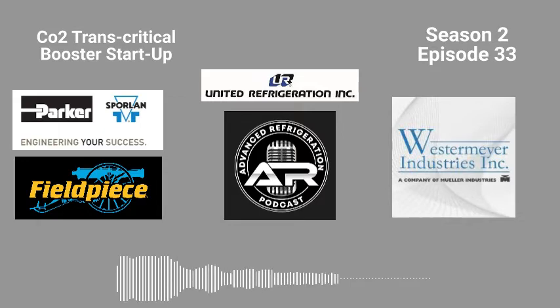So what we do is I generally pull the reliefs. On the flash tank, I will pull one relief off the relief tree if you have one. Depending, the last 2 racks that I've started up had no relief trees. So you blow the relief, you blow the charge. I will pull the relief and thread in usually a 1/2 by 1/2 inch male pipe thread by male flare, and I'll put a blue vac hose right in there. That way I'm pulling full flow 1/2 inch right off the top of the receiver. Then I'll put one on the suction headers, one on the drop leg, and then on a TC discharge if I can get it. And then you'll pull down the whole rack that way.